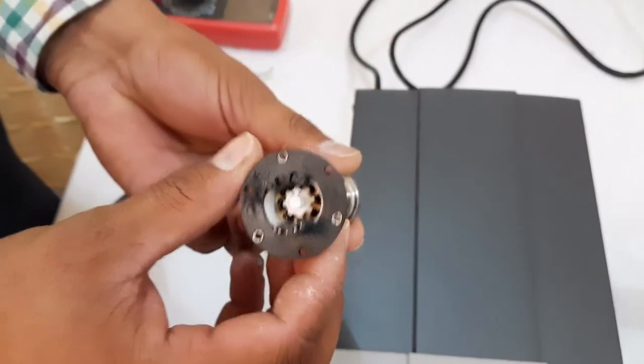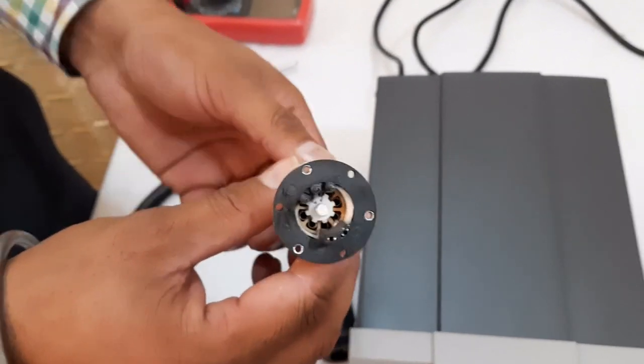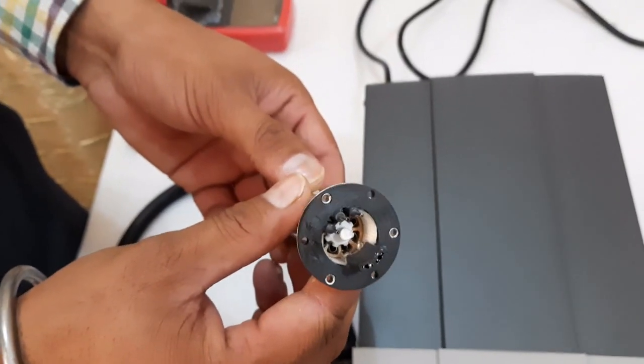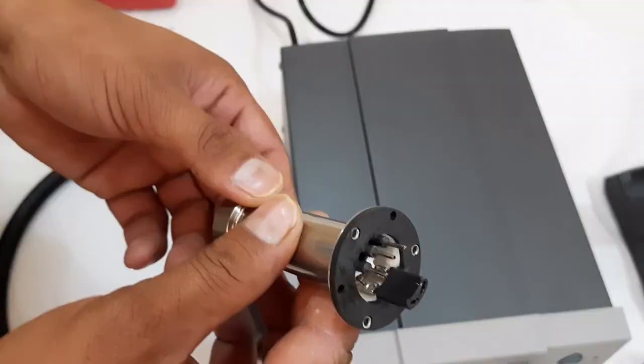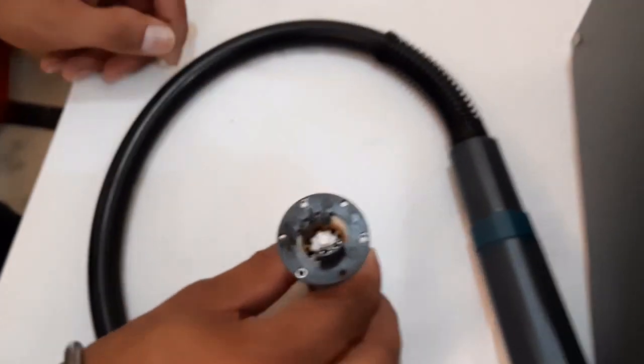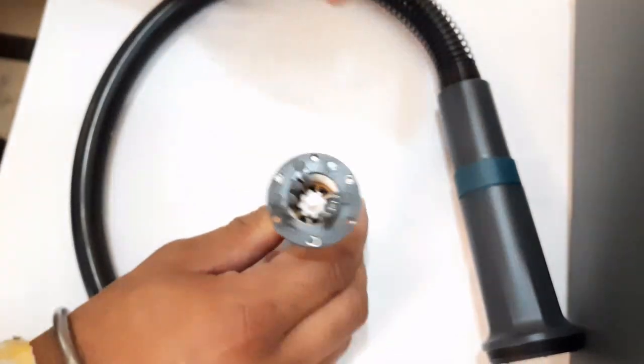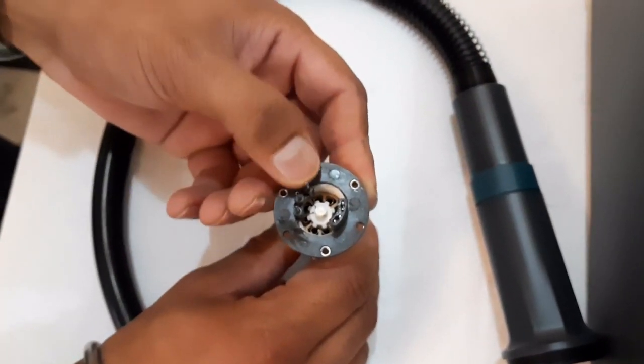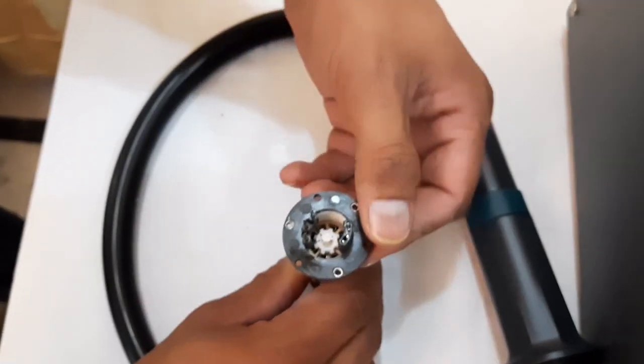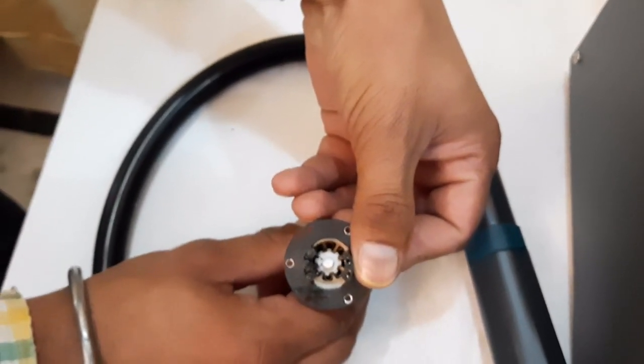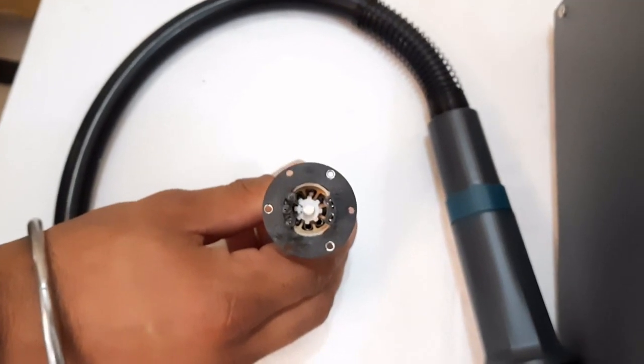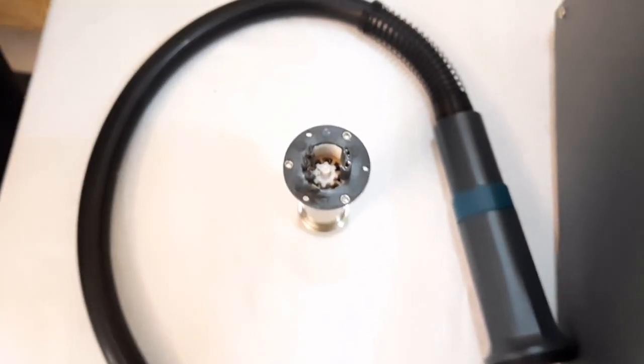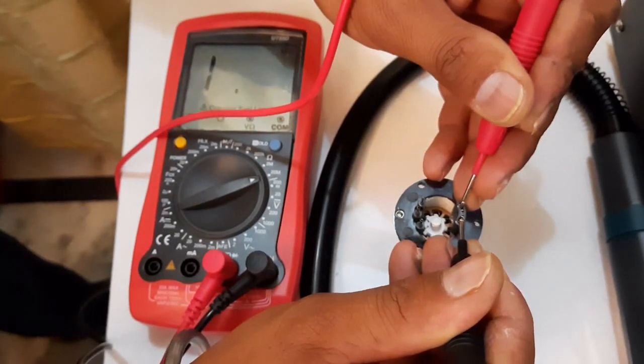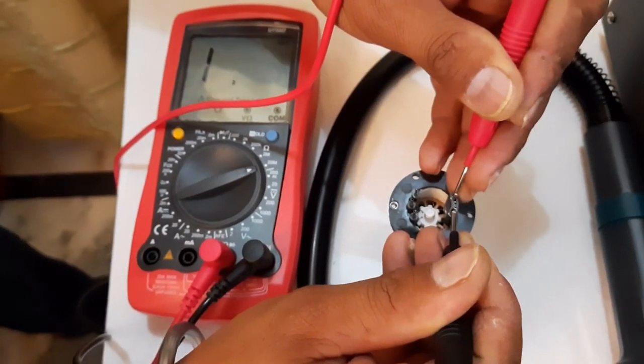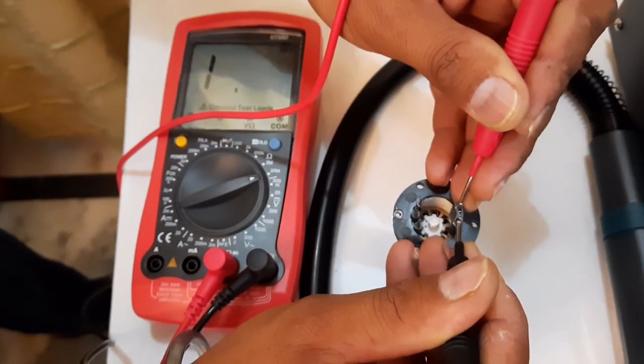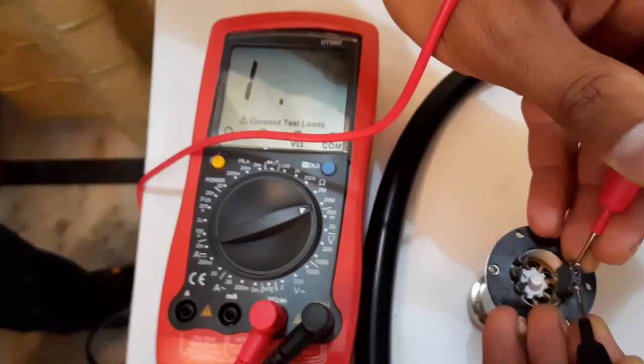See, this is an integrated type of heating element. Both the sensor and heater are embedded inside this enclosure. These two pins are connected to the heating element, and on the other side these two sockets are connected to the sensor. So first we will measure the resistance of the sensor using a multimeter. Ideally it should be less than 50 ohm, but it is visible that it is more than 50 ohm. It means the sensor is faulty.